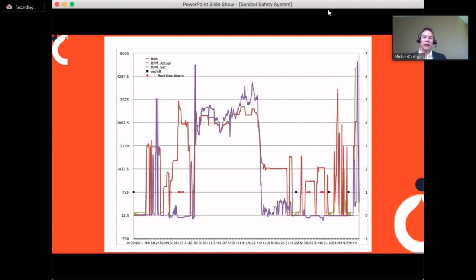In this case, this graph and all the data points presented helped us understand that the perfusionist had been experimenting with different clamp placements for initiation of bypass. And what they thought was an oxygenator thrombosis was in fact an errant clamp left on the arterial line.